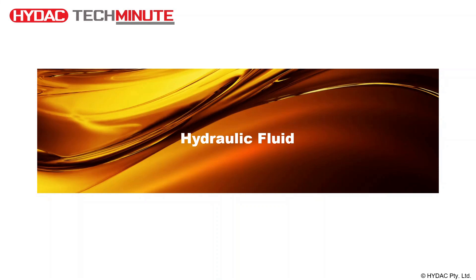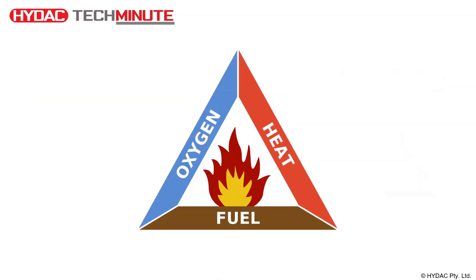Combining the drop in auto-ignition temperature with the potential atomizing of hydraulic mineral oil and the high temperatures created by gas compression, there is an inherent risk of spontaneous combustion, which can lead to explosion. However, in order for combustion to occur, three things are needed: heat, fuel, and oxygen. This is where nitrogen is used — without oxygen being available, there can be no spontaneous combustion.